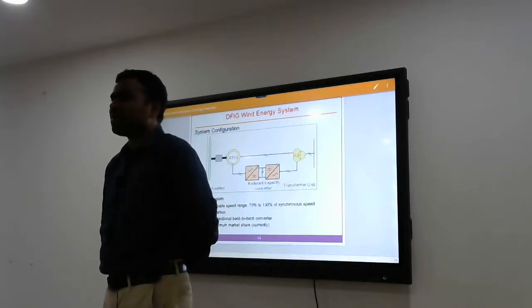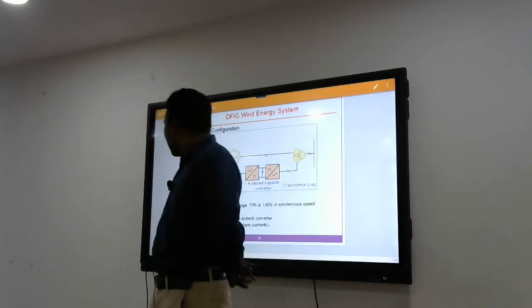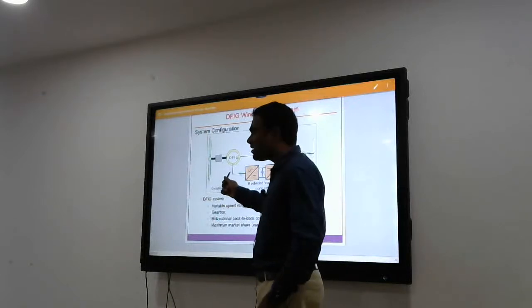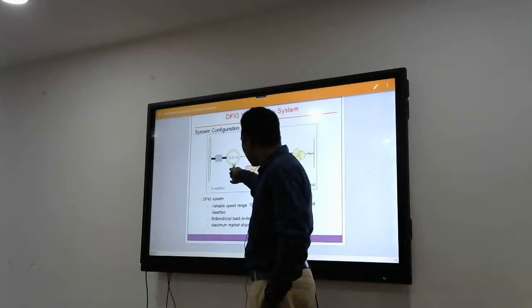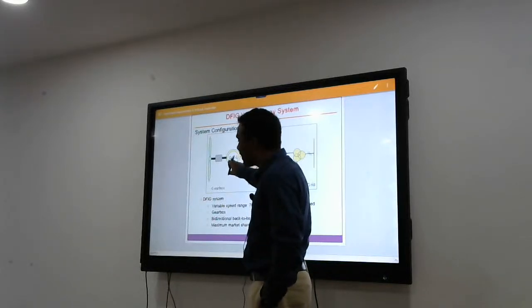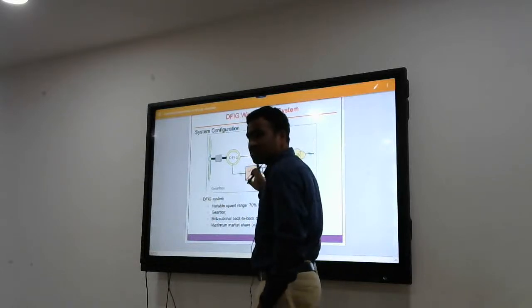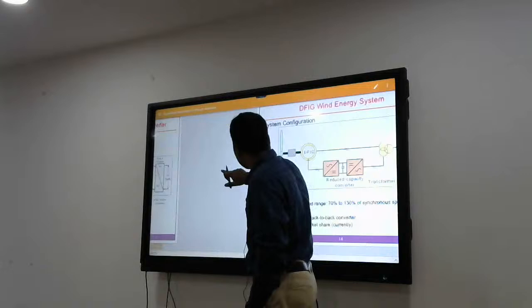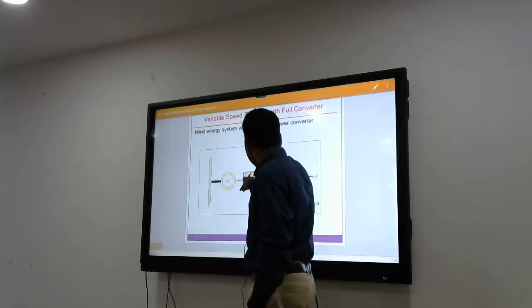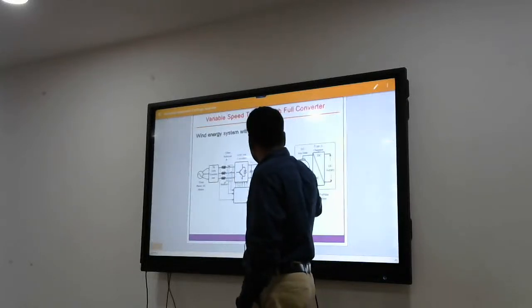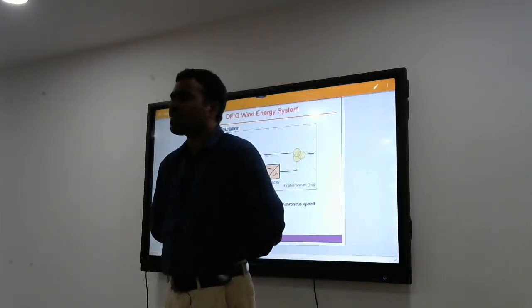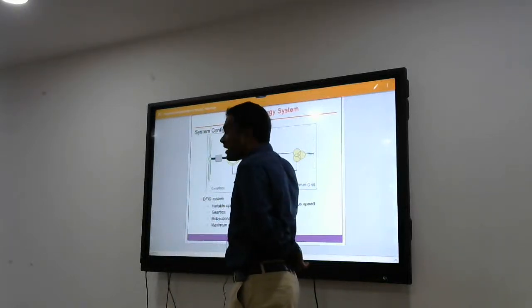Now it comes to the main topic, which is the doubly-fed induction generator, or otherwise the wound rotor induction machine. There your converters are not connected on the stator side, but on the rotor side. If you see, this is DFIG, meaning wound rotor induction machine. In this wound rotor machine, the stator is directly connected to the grid, and in the rotor you have two converters connected. In the previous case, for simplicity, these converters were connected in the stator, but in this case, your converters are connected in the rotor. How does it matter? Yes, it matters a lot. If my slip is less, then my converter rating will be less.